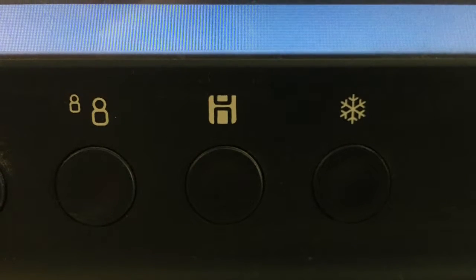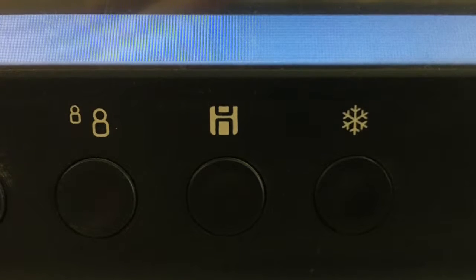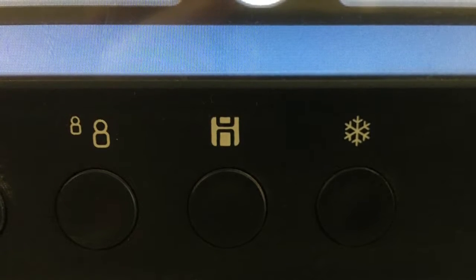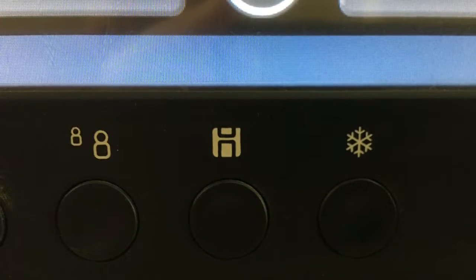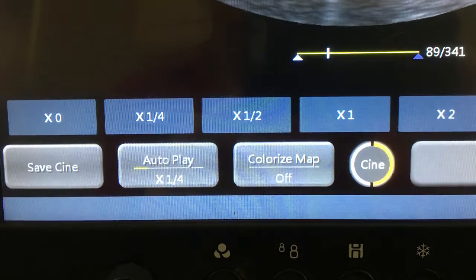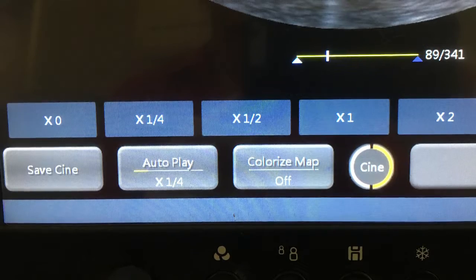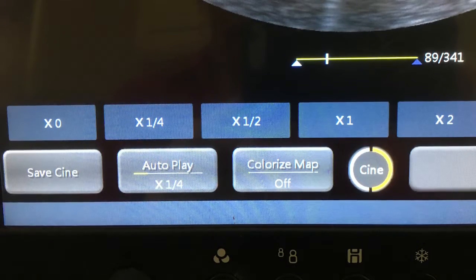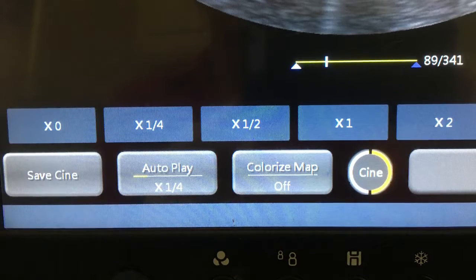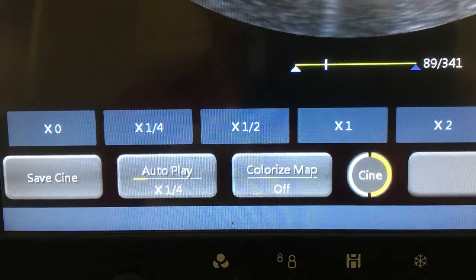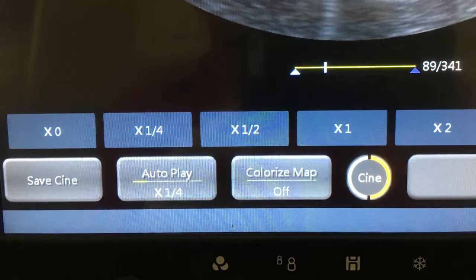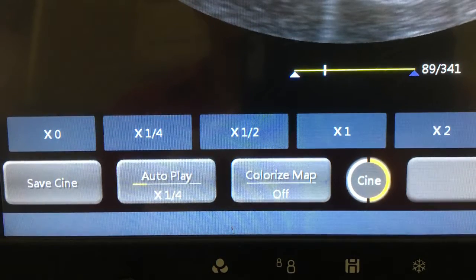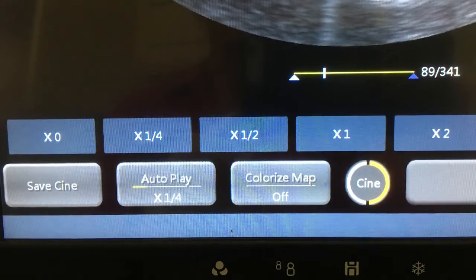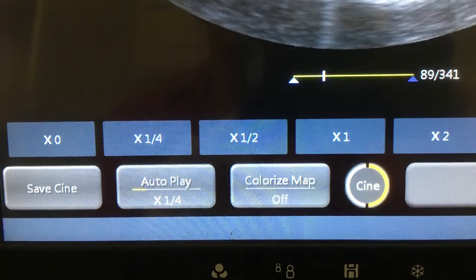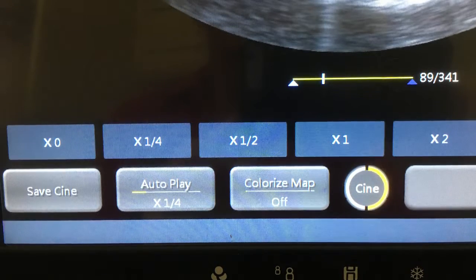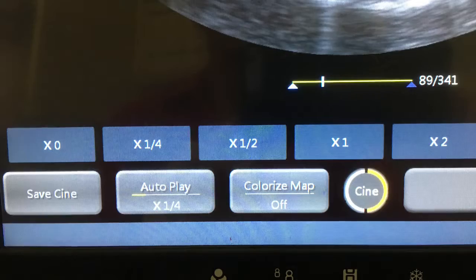As well as using the freeze button on the control panel to freeze an image on the cine video, use the same button to unfreeze and return to video function. When the cine video on the screen is frozen, you can either save it by pressing the save icon in the control panel, or press Save Cine on the screen, or you can replay the cine by pressing autoplay, then selecting the speed you want to see it, either 1/4, 1/2, normal times 1, or speeded up times 2. Once you've finished reviewing the video, press times 0 to stop the video.